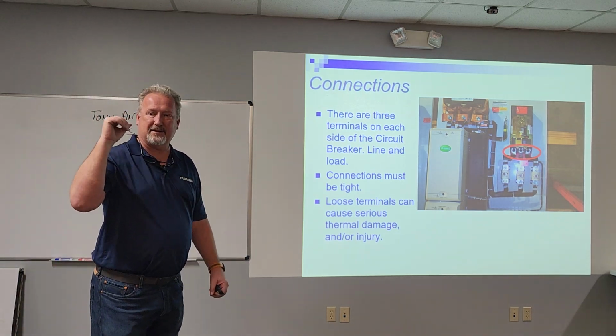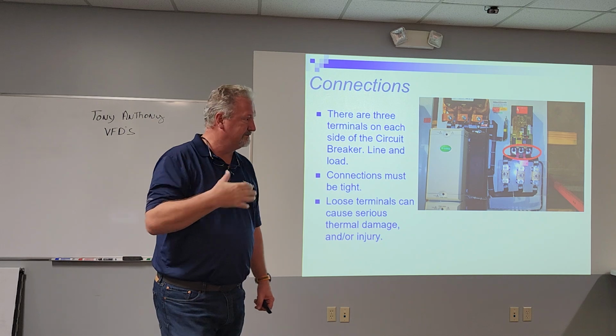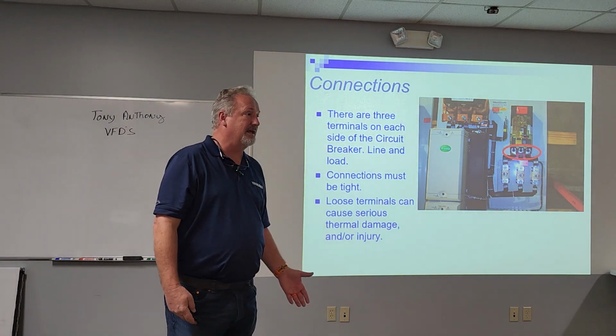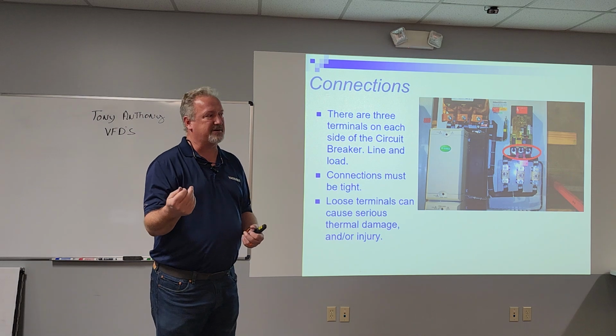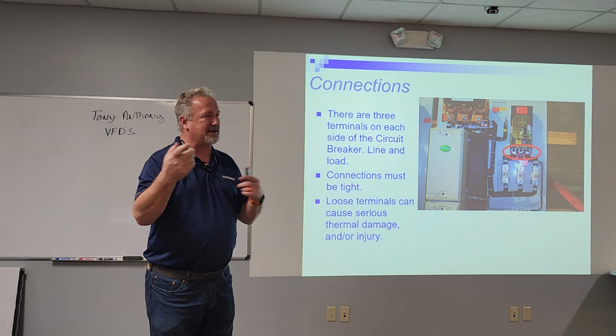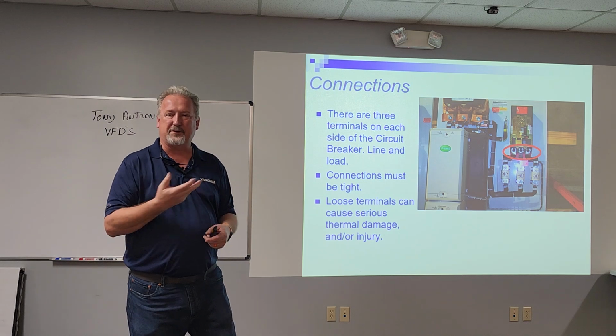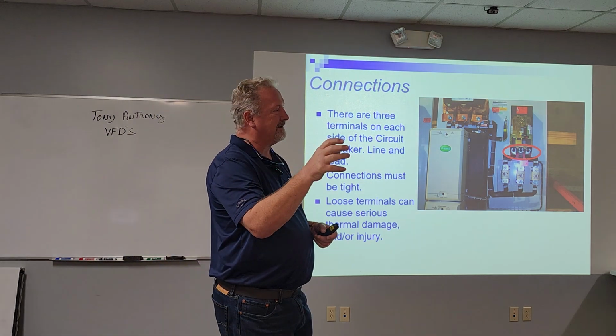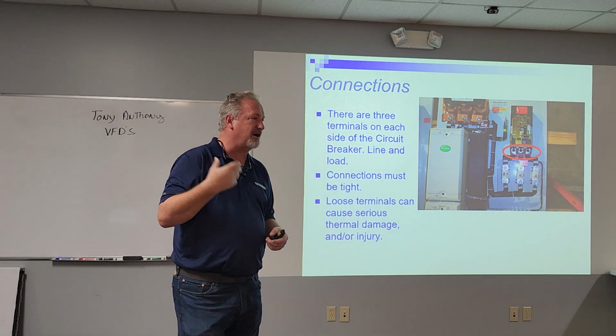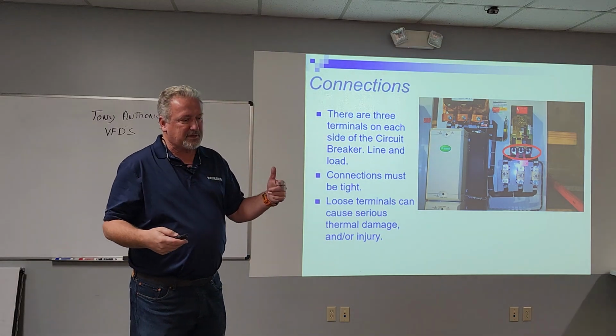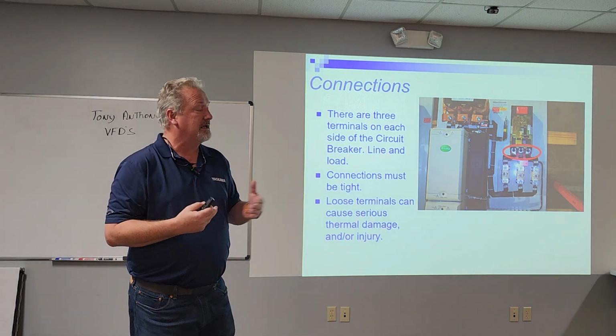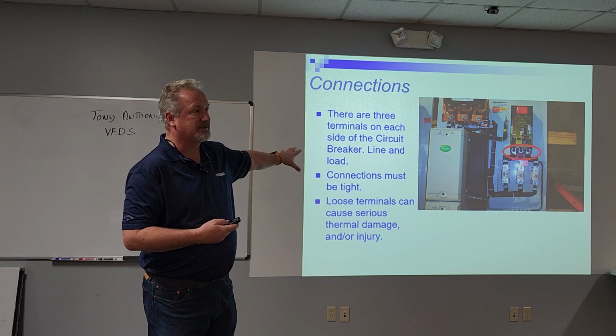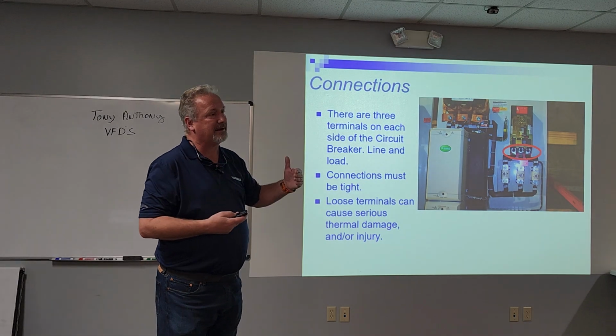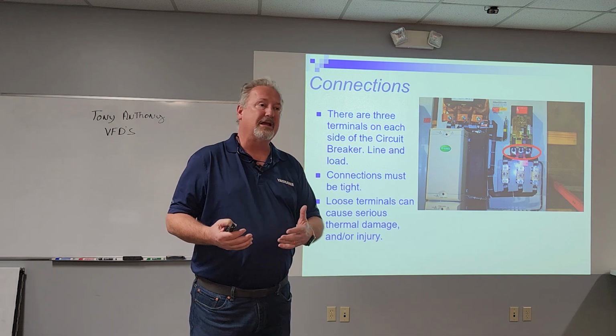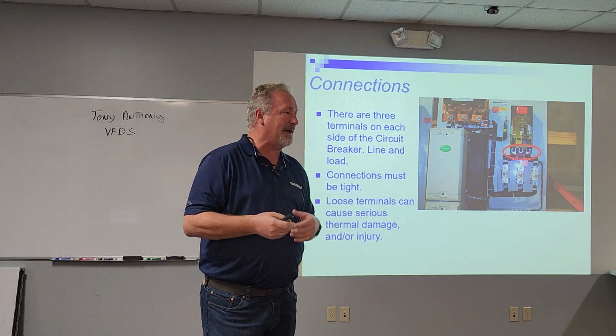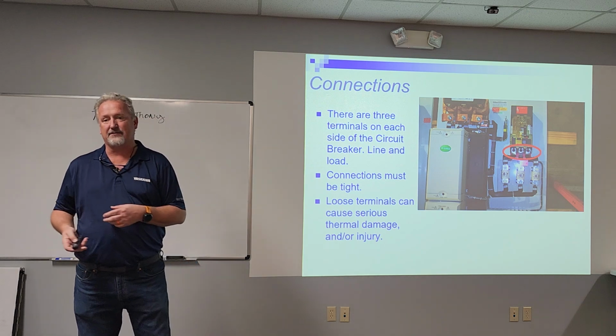You may have had customers where you have a thermal gun to check for hot spots. That's usually caused by loose connections. If you think about it, especially if you've got a stranded wire that you crimp down, every time you start that drive, current's flowing through it, and that's heat. That cable is expanding, contracting, expanding, contracting every time you operate it. So it's going to slowly work loose. One of the ways you can protect your customers and prevent some headaches down the road is, if you've installed a piece of electrical equipment and you're back in there a year or so later, get in the habit of retorquing the main connections at least. It'll save you a lot of headaches down the road.